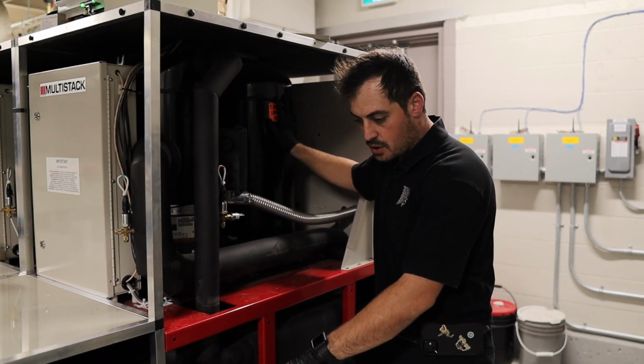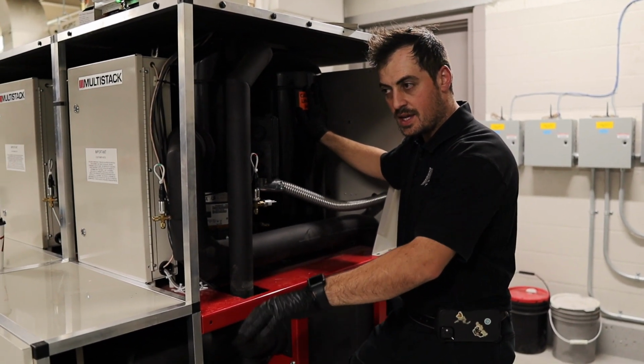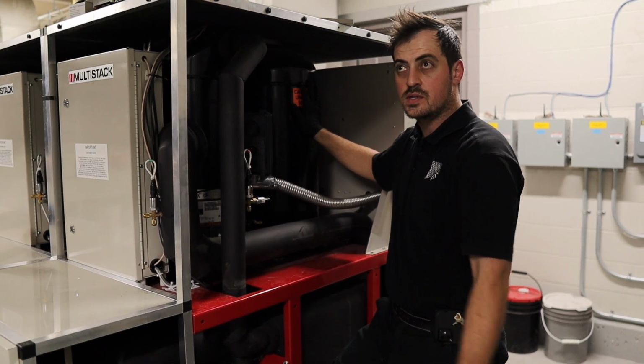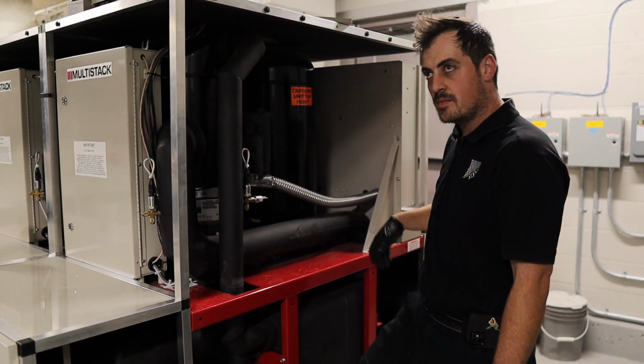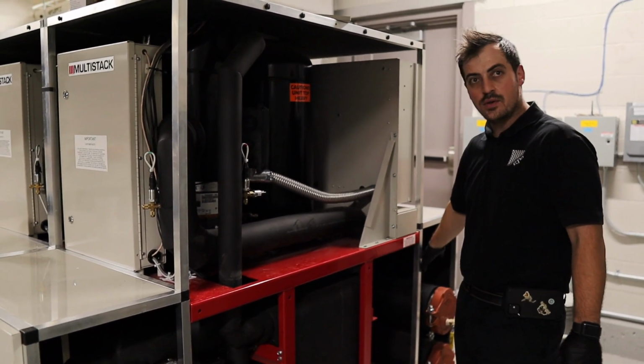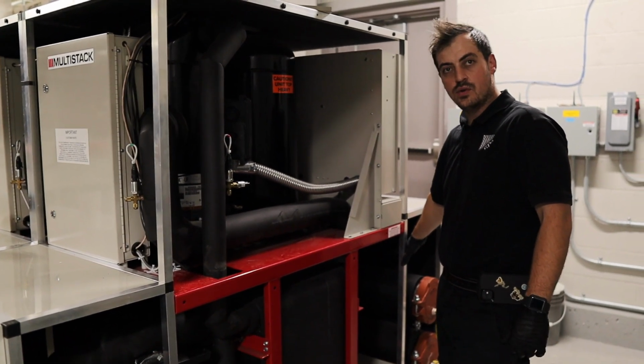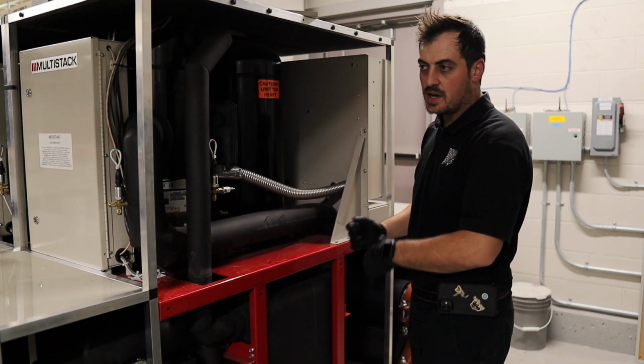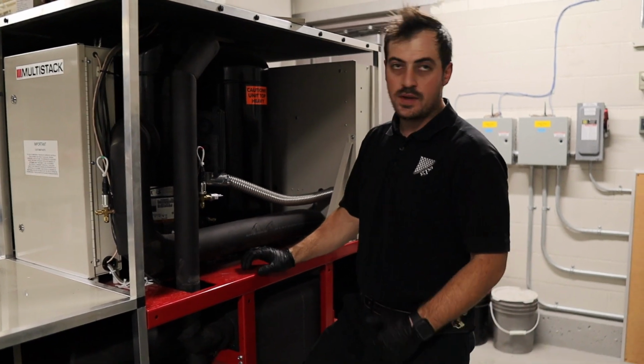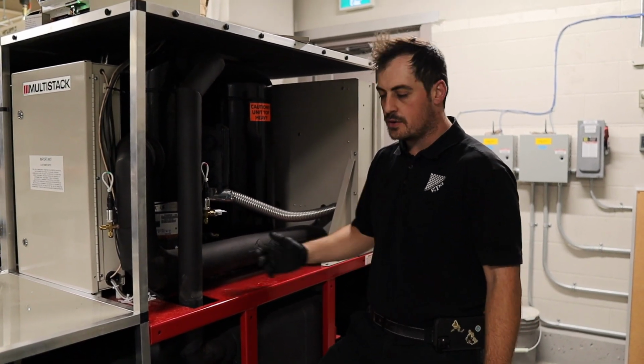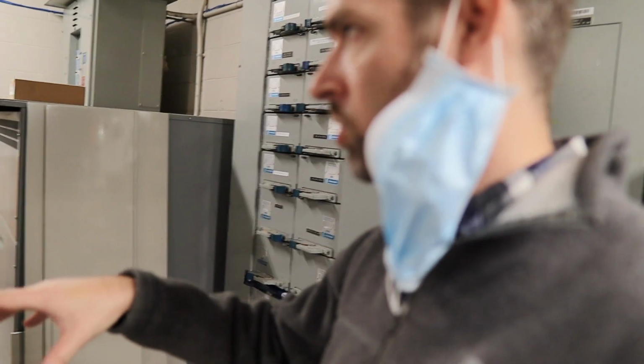And you're constantly creating heat to be used somewhere in the building, and at the same time, you're cooling down the water to be utilized for cooling somewhere. So you're effectively transferring energy, whereas in the heat pump you're taking that heat from the ground or another source. Okay. So we can essentially control to either the condenser or the evaporator with the heat recovery chiller.